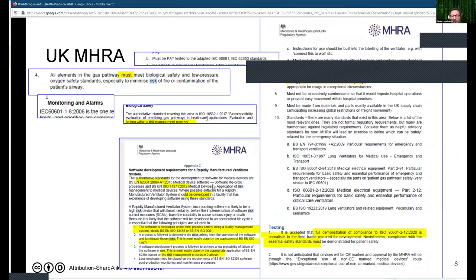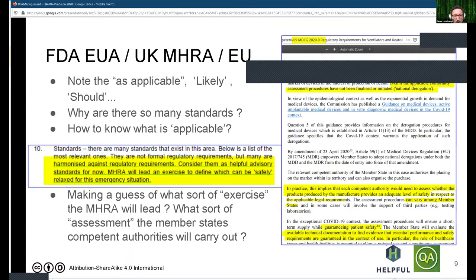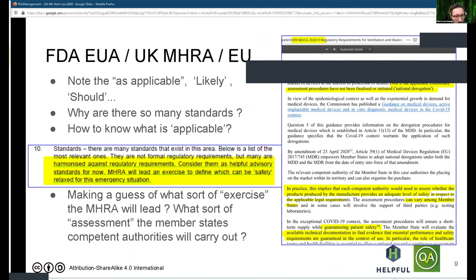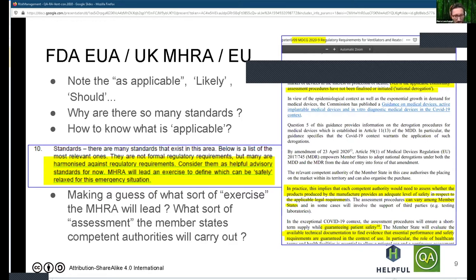What I found interesting in these EUA and MHRA documents is the use of terms like 'as applicable,' 'likely,' and 'should' — terms you don't see a lot in standards generally, where you see much more 'shall' and 'must.' That's because these documents are meant to adapt to an emergency situation where you cannot just follow the usual red tape process. When you think about what sort of process the regulators themselves follow to identify what has to be done as opposed to what could be left aside, they will be using a risk management process themselves, focused on policy rather than devices specifically.